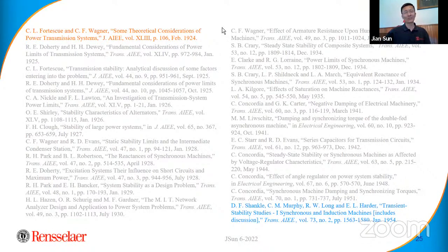If that negative real part is negative enough, it will eat all the positive damping you have in the network, and you get an unstable resonance somewhere, and that will create a harmonic. So you don't have to have pre-existing harmonic to be amplified. That unstable resonance is why a lot of the pictures show initially a clean waveform, and then harmonics start to grow and grow.